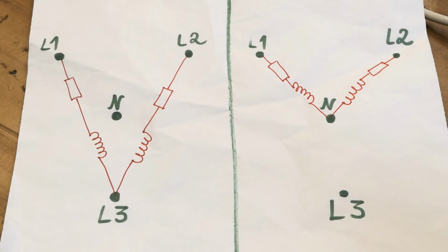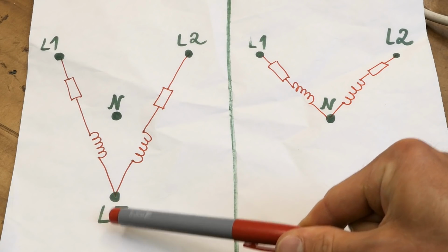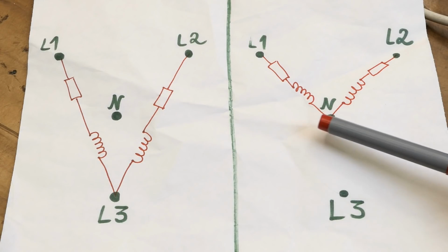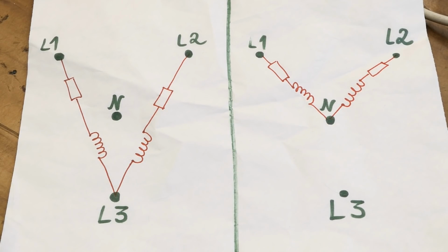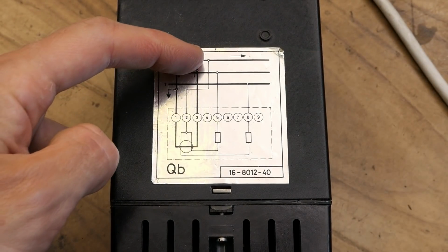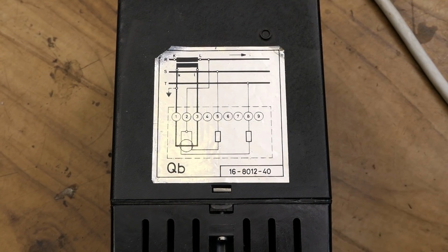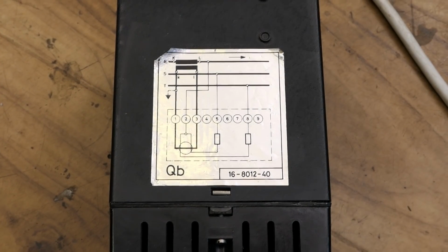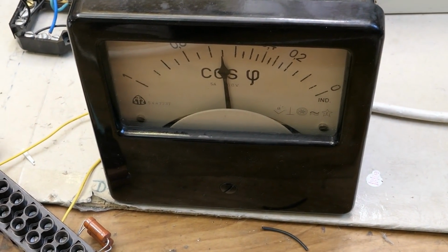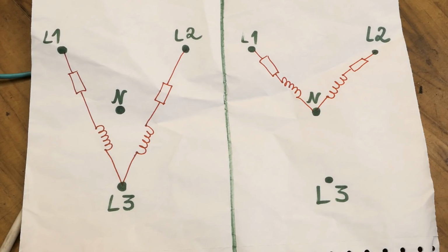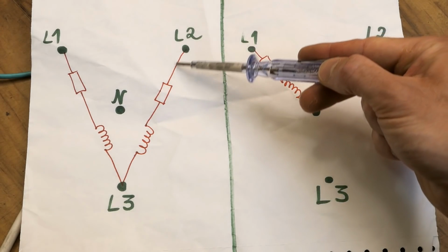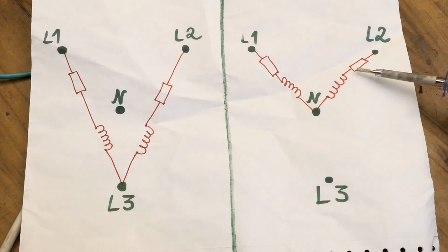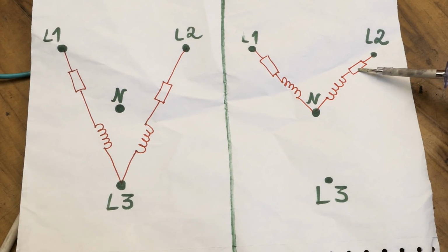Instead of connecting the voltage coils this way, the center point to the last phase, I connected the center point to the neutral. In this one, the center point goes to the last phase, the one that's sensed, where the current sensing is, but maybe this one has to have the center point connected to neutral. This of course changes the angles of the currents, and it also lowers the dissipation of the resistors while supplying the same current into the coils. Because here it's dropping the voltage from about 400 volts and here from just 230 volts.